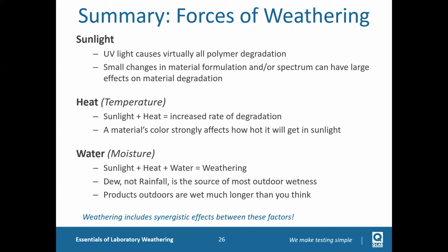The quality is good. But if you put that plastic directly outdoors, it will show fading or chalking or gloss loss very quickly. Why is that? Because the plastic is designed for indoor. Indoor has indoor SPD, which is different from outdoor SPD. So when we talk about our Xenon, I will introduce why we have different kinds of filters. Heat in here actually is not the cause of weathering, but it's the acceleration factor of the weathering test. Water.